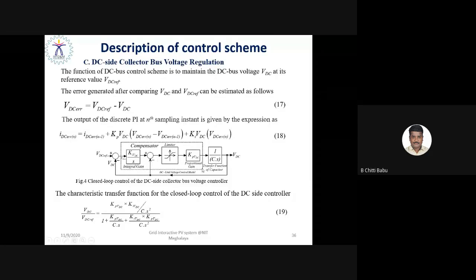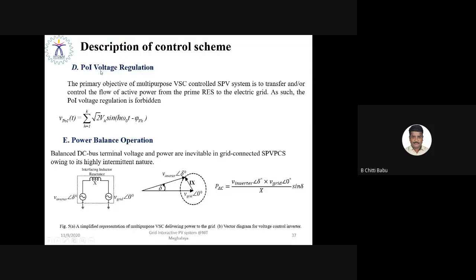The controller is designed with optimal gain values of Kp and Ki, so you are able to regulate the DC link voltage in a precise way. The corresponding transfer function between the DC link voltage and the reference DC link voltage is given in equation number 19. And as you are regulating the PoI voltage, I mean the AC voltage, that has to have an instantaneous three-phase voltage of 415 volt, line to line, and it should have only the fundamental component.